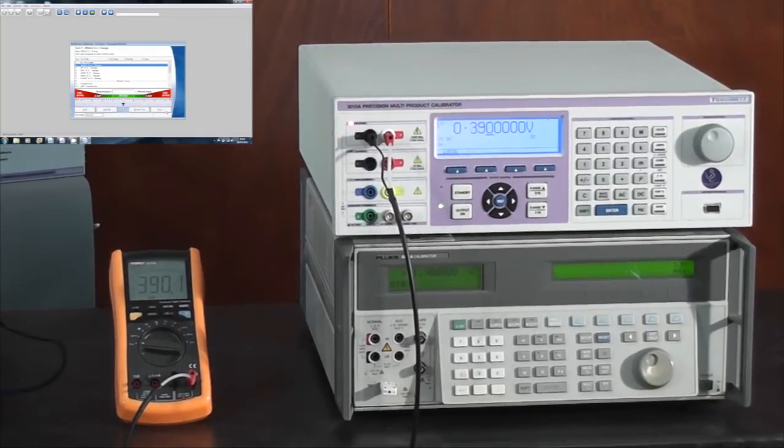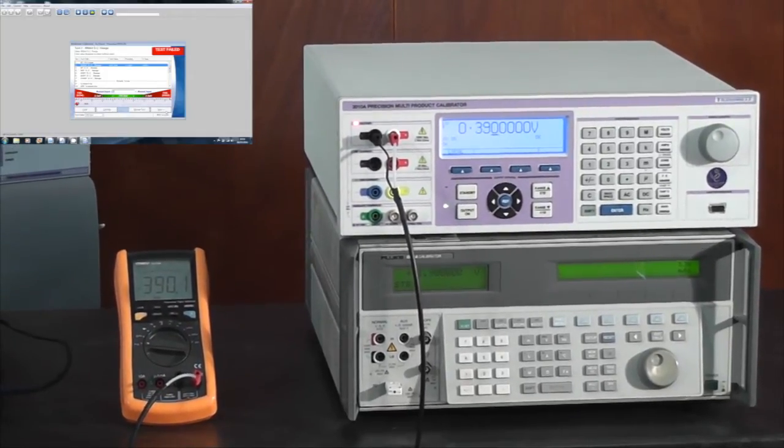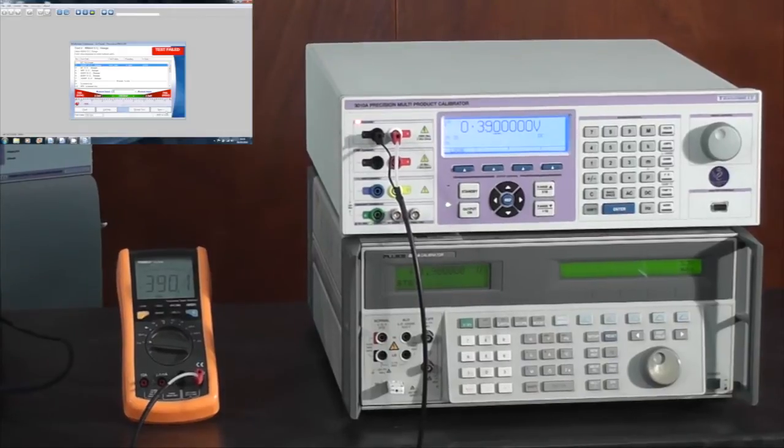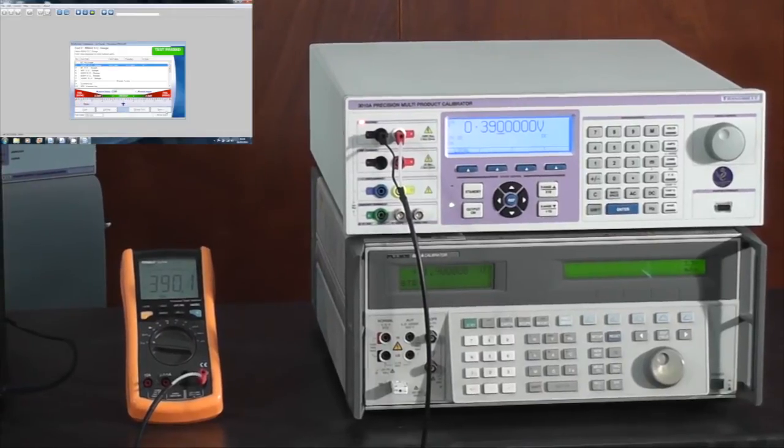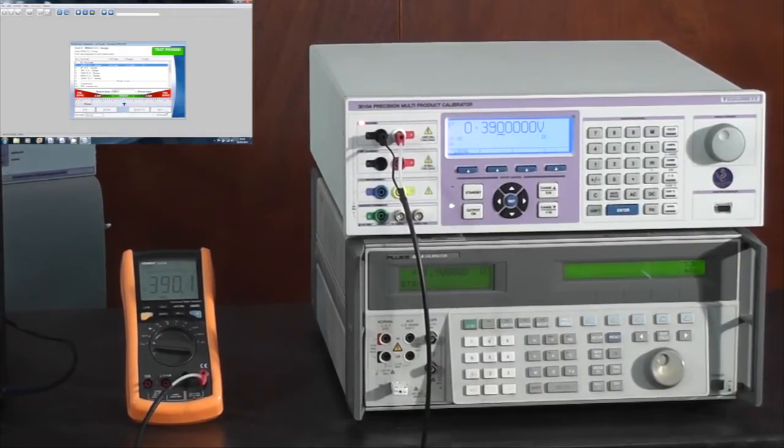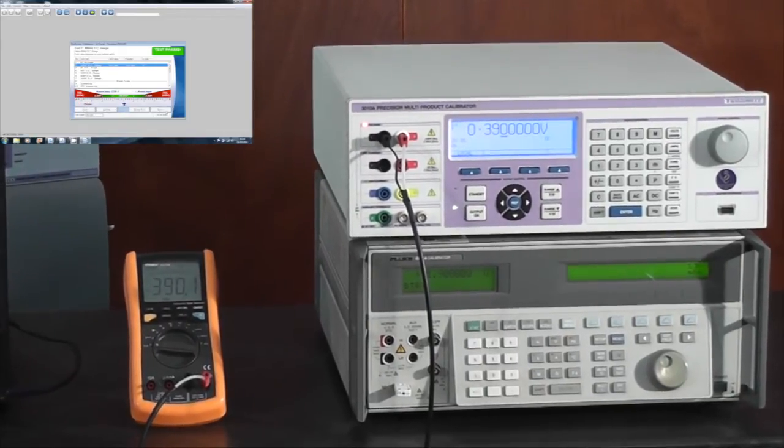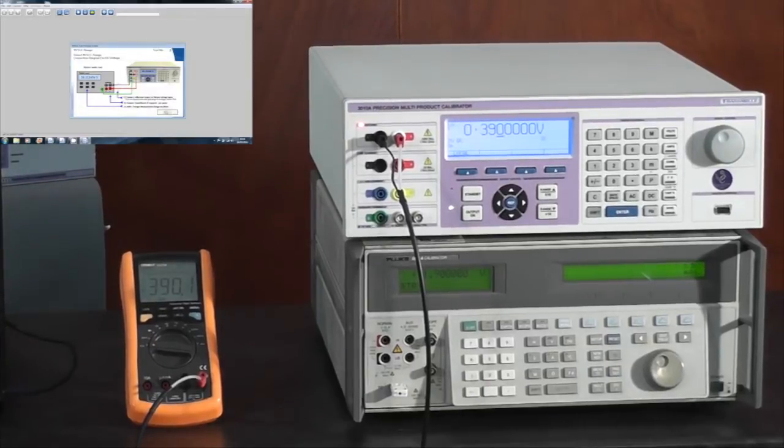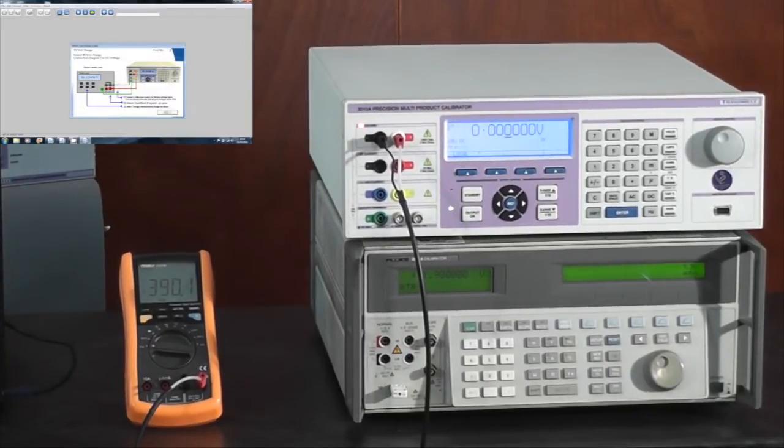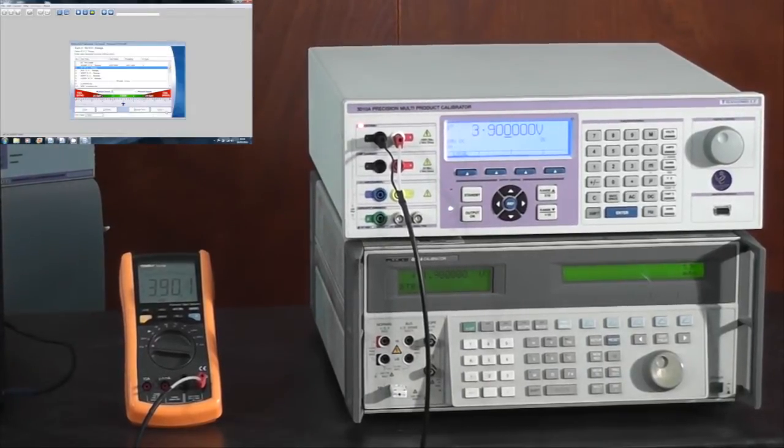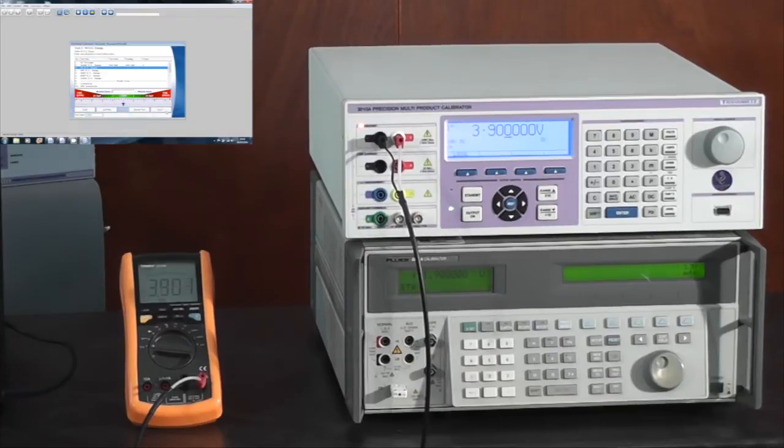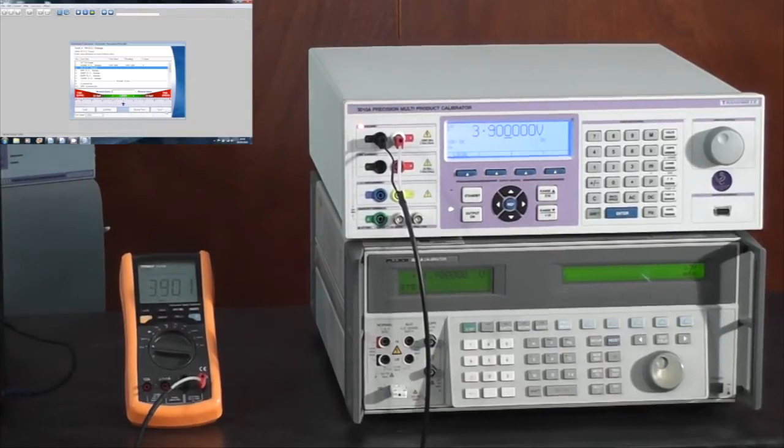I press next and the 3010 has automatically set the correct output. All I simply do is type in the value displayed on the multimeter, press the enter key, observe the next prompt, and once again the calibrator has automatically set the next output.